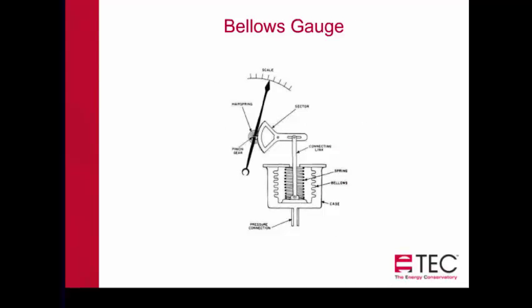A variation is the bellows gauge. As pressure is applied into a piston area, as that area fills up, the bellows compresses. The compression is linked to a mechanical mechanism, which is further linked to a needle. A scale is created behind that so that when pressure is exerted, the bellows pushes up, moves the linkage, and increases the scale reading.